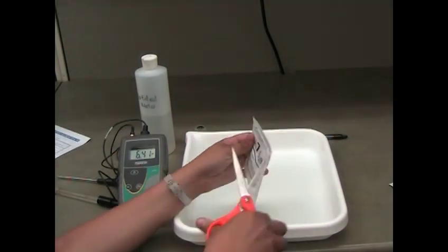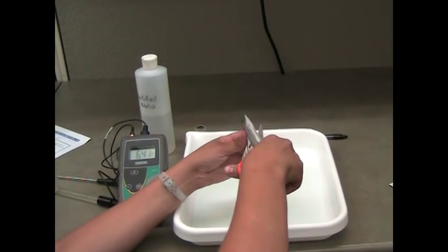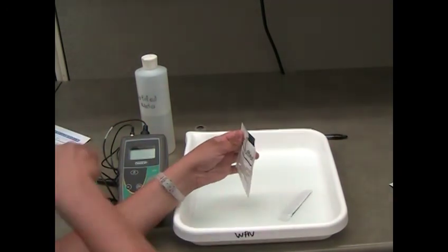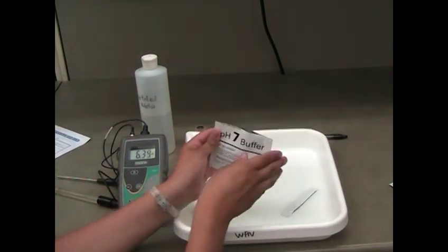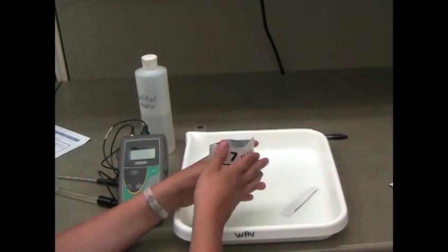Open the packet with the pH 7 buffer solution with a pair of scissors. Place the electrode and temperature sensor in the pH solution and submerge the electrode bulb completely.